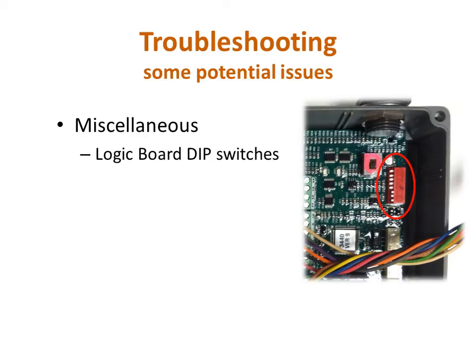Another thing that can be checked while the logic box is open is the white sticker on the board that lists the model of monitor the board is programmed for, as well as the version of software that is used. This is more likely to be a possible factor with a replacement board or for initial setup, as compared to a unit that has been in service for a while and has developed a problem. It's still worthwhile to know where it is and where to find it though.